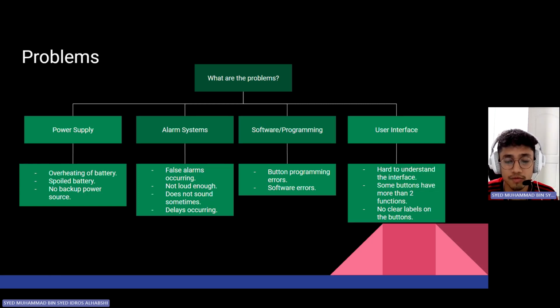And if they check the infusion pump and there is no problem with the pump, they have actually wasted a few minutes trying to resolve the problem and actually pause the infusion pump. If the patient is in a critical condition, this may actually affect their health as well, as they are not being pumped the amount they need and is actually being interrupted by these false alarms. For the alarms that are not loud enough or do not sound sometimes, it may actually result in the patient's condition being worse, as they cannot take immediate action as they cannot hear the alarm, and this is very bad for the patient.